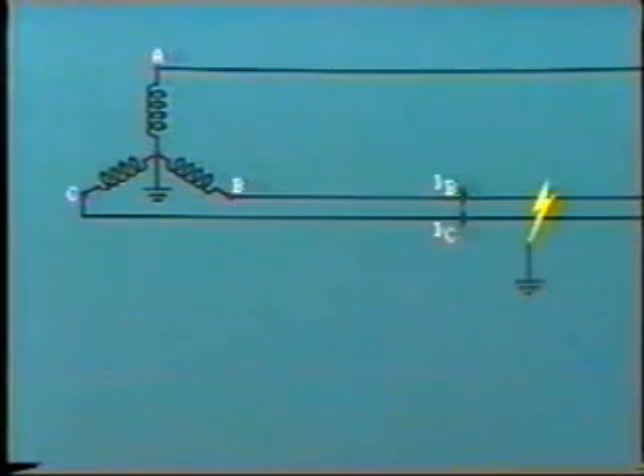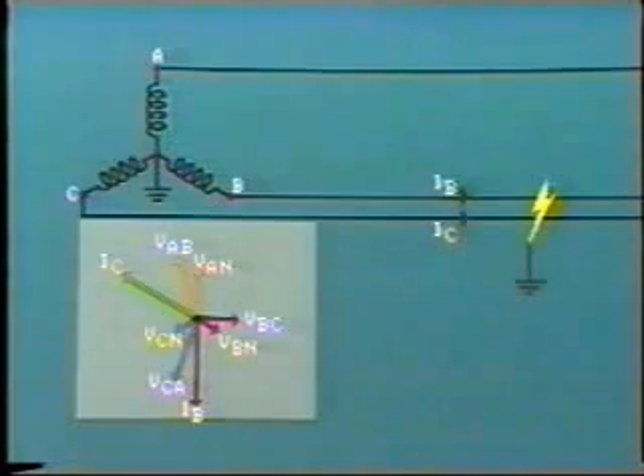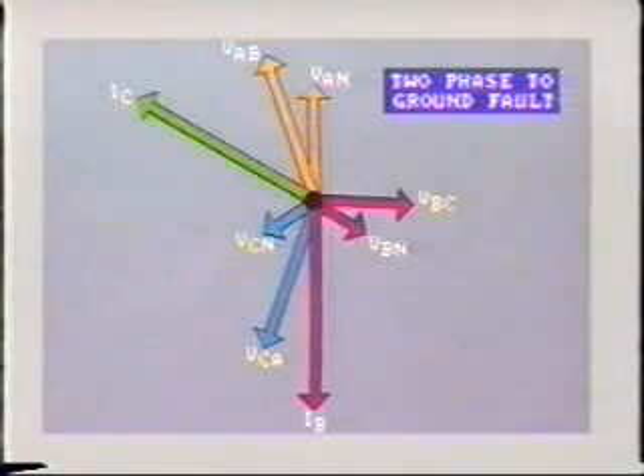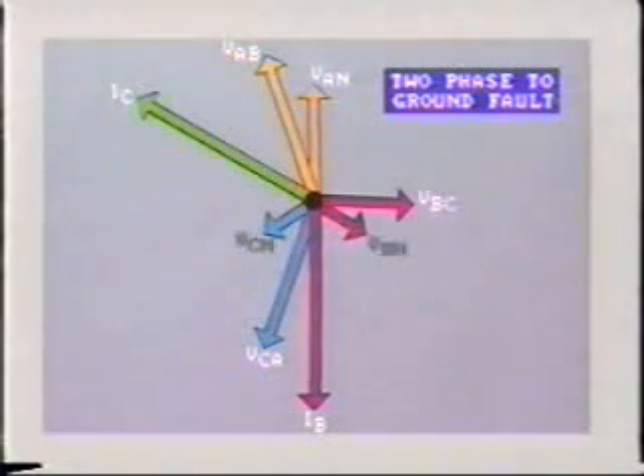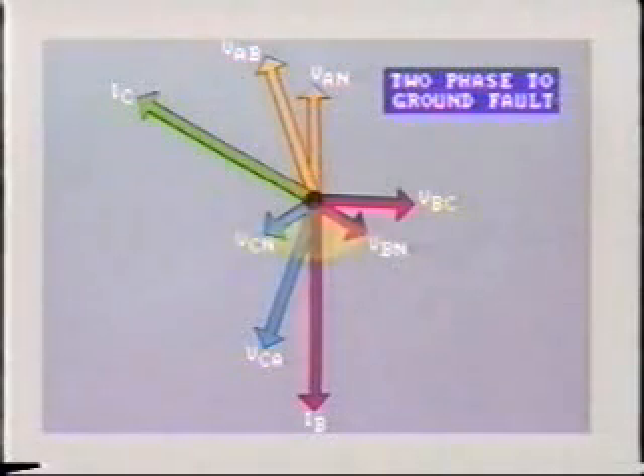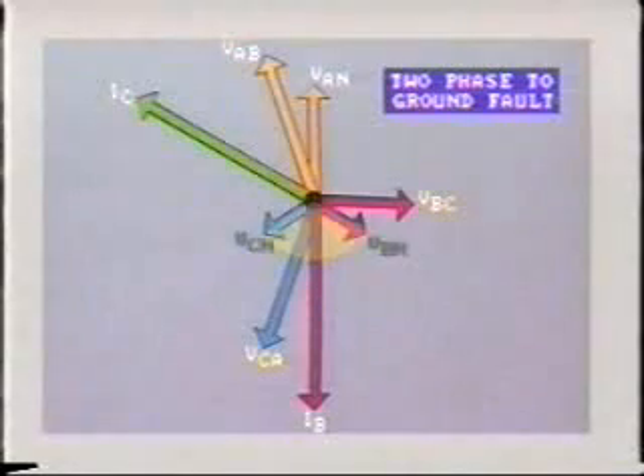Yet another common fault is the two-phase to ground. This example shows a fault between lines B and C, which in turn is faulted to ground. We have currents IB and IC flowing to the fault, and IG, the ground current, leaving. Thus, IB plus IC equals IG. The resultant phasor diagram is similar to that for the phase-to-phase fault, except the depressed voltages VBN and VCN remain at their pre-fault phase angles.